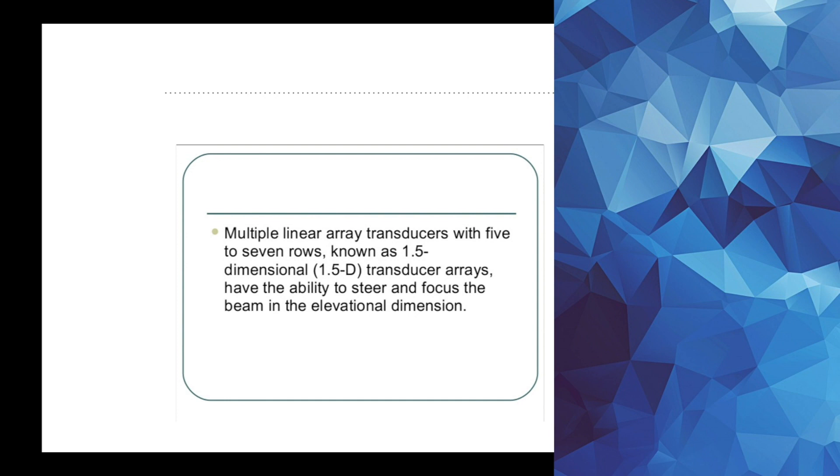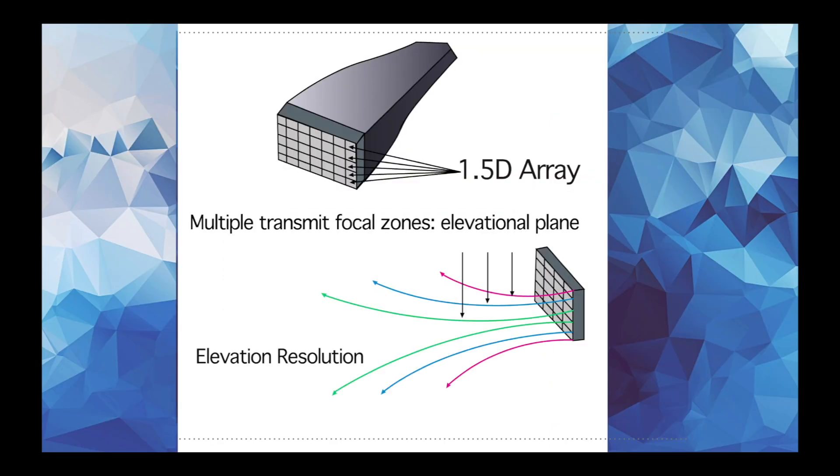So just specifically, if you can cement in your mind 1.5D with elevation thickness, that's pretty much what you're going to need to know. And let me show you what that means. So 1.5D will have not only columns of crystals, but it'll also have the rows of crystals, and typically there's going to be five to seven rows of crystals.